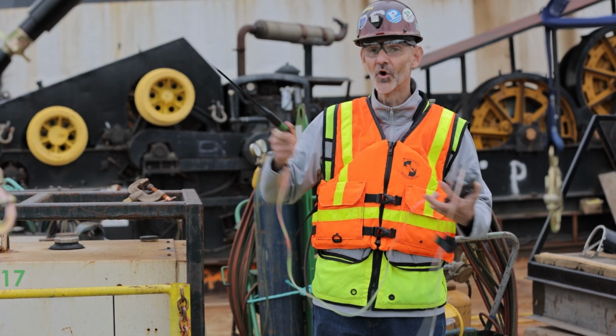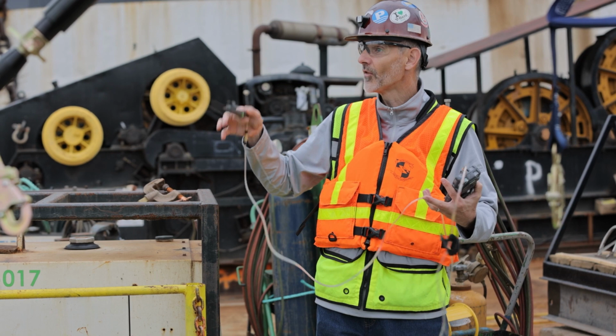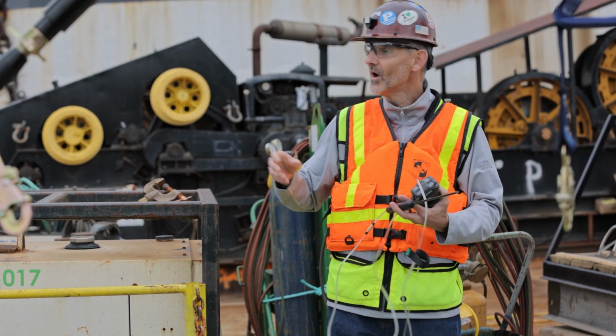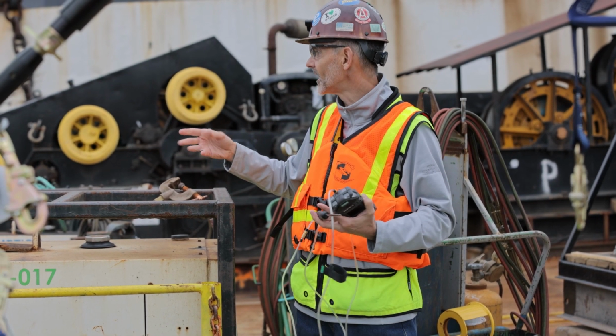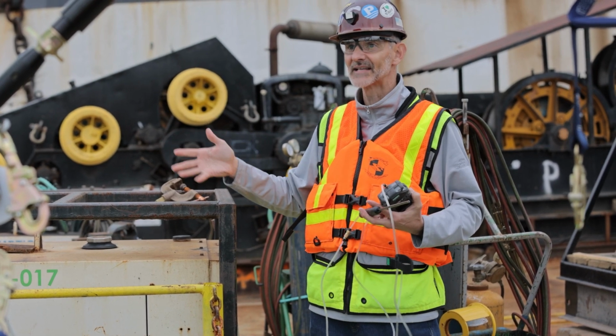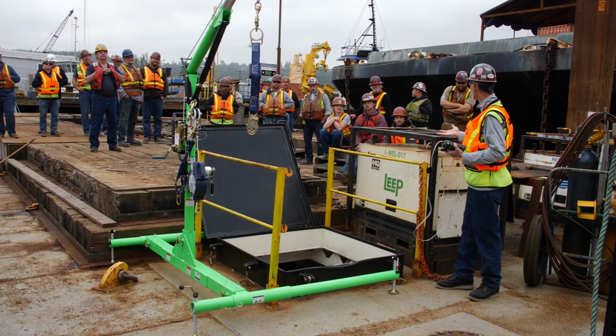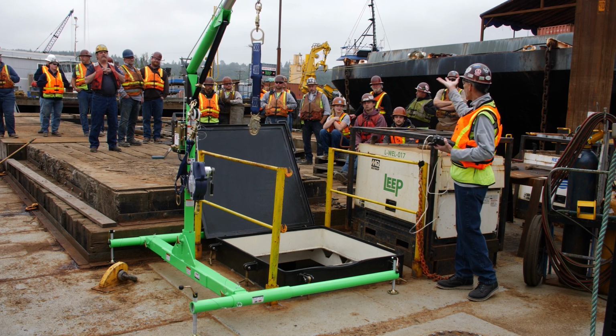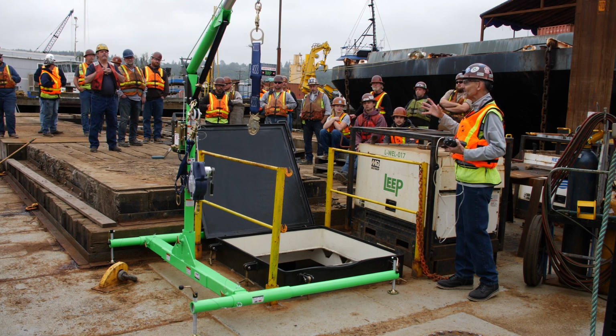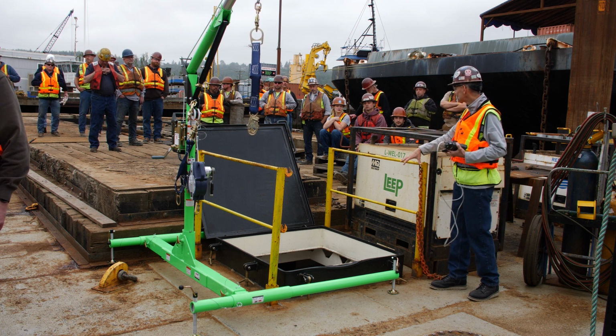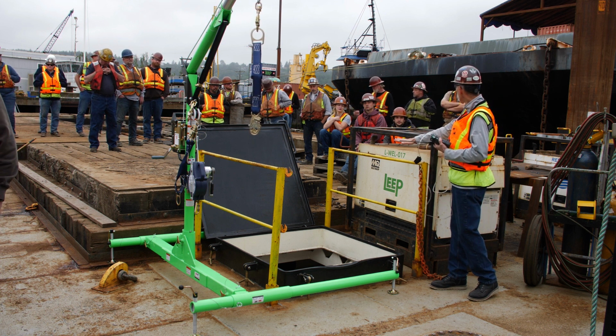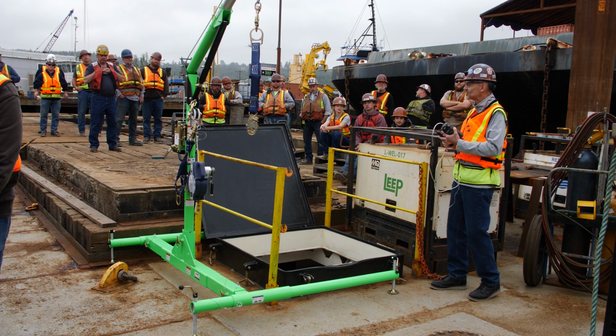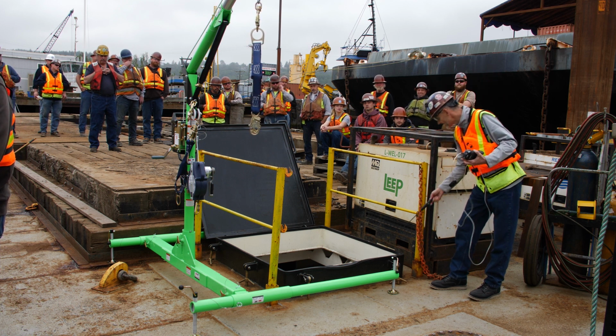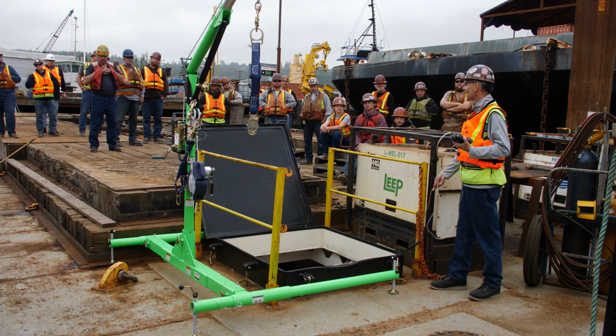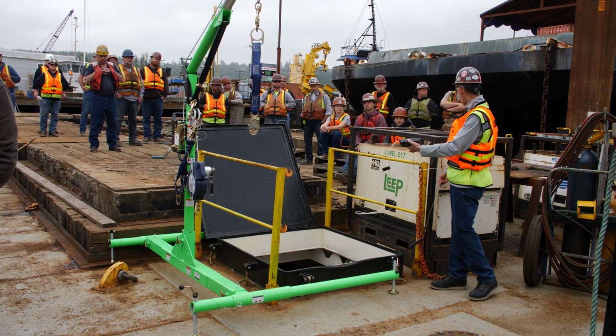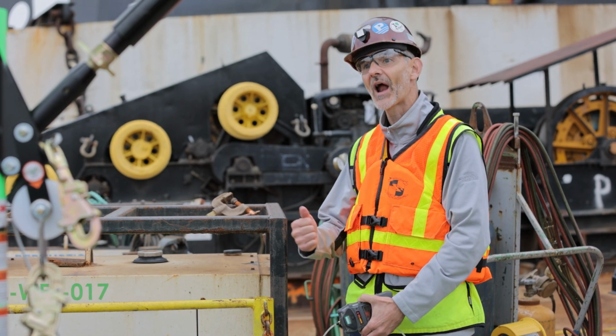But first thing we're going to do is send this all the way down to the bottom. And I will say too, explosive gases, acetylene, methane, those sorts of things are lighter than air, so they tend to come up to the top of a space. So if you can, and there is space to test underneath the lid or a manhole type of situation, always a good idea to send this underneath and check to make sure that there's nothing at the top, okay? Particularly if you're having to pop a lid.